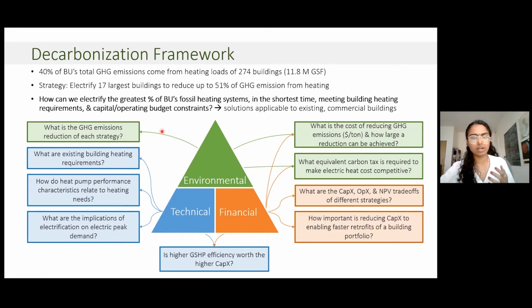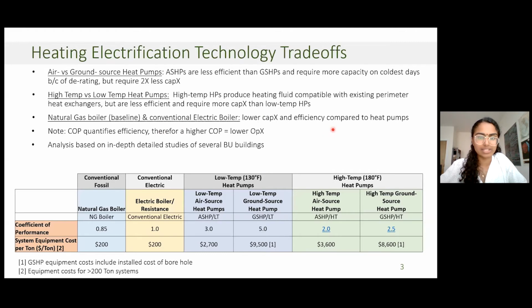In order to achieve this sort of decarbonization, the first thing I'm going to touch on is different heating electrification technologies, and these are ones that have been discussed earlier in the seminar as well. Generally, the two categories of electrification systems we've been looking at are heat pumps and boilers. In between them, you'll notice that heat pumps have a much greater efficiency, but are also much more expensive than boilers are. Within heat pumps, you'll see different categories, air source versus ground source, and this distinction is made based on where they have their thermal reservoir. Air source heat pumps are less efficient than ground source heat pumps, but are also about 2 times less capital intensive.